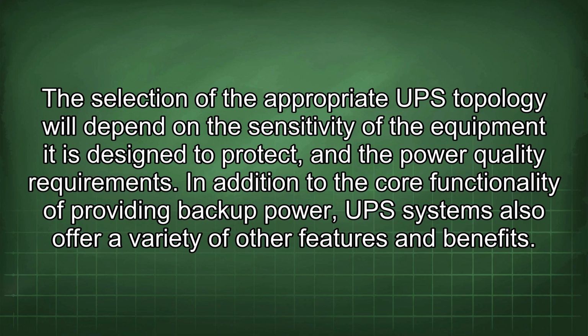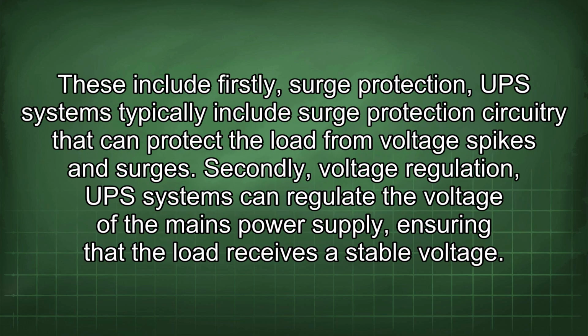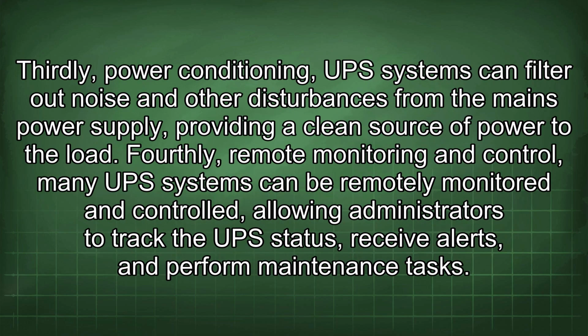In addition to the core functionality of providing backup power, UPS systems also offer a variety of other features and benefits. These include, firstly, surge protection. UPS systems typically include surge protection circuitry that can protect the load from voltage spikes and surges. Secondly, voltage regulation. UPS systems can regulate the voltage of the mains power supply, ensuring that the load receives a stable voltage. Thirdly, power conditioning. UPS systems can filter out noise and other disturbances from the mains power supply, providing a clean source of power to the load.